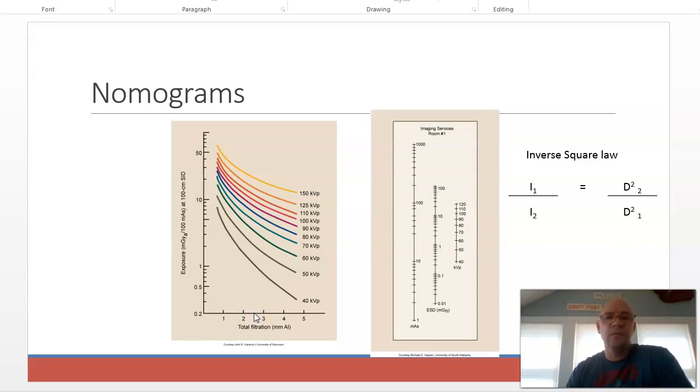So let's pretend we're doing an exam with 60 kVp. If I raise my mouse up to 60 kVp, that goes onto this graph here because it's based on 60 kVp. And then I move over to the left, and I'm getting approximately whatever this line is, or around these lines. So 1, 2, 3, say 3.5.